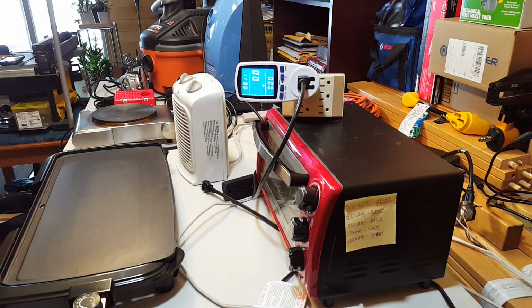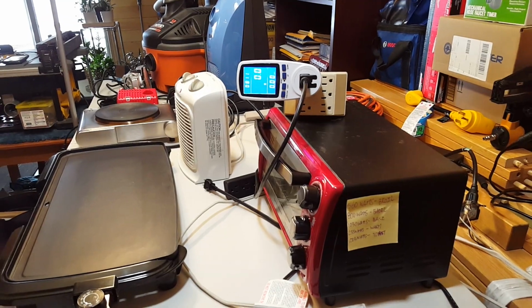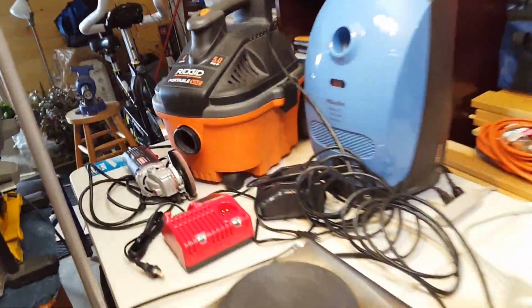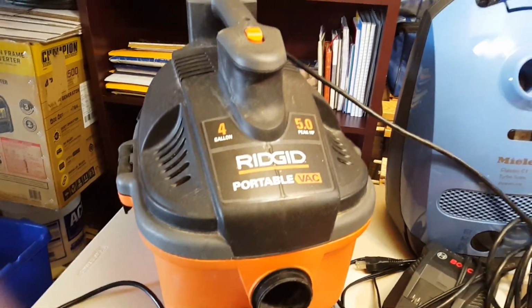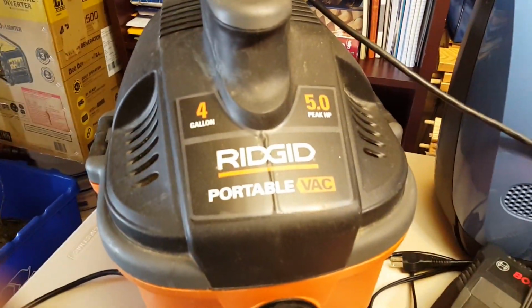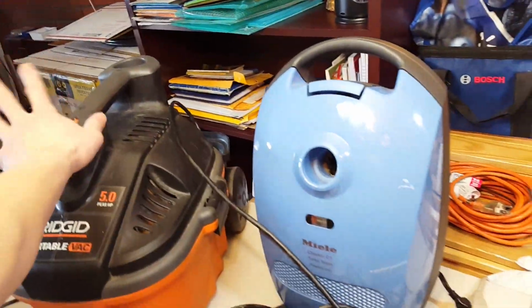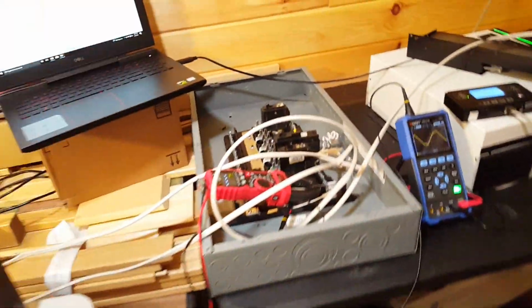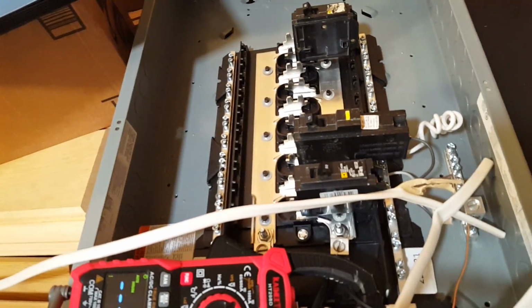We're going to look at surge, AC surge, and DC surge for the motors now. We'll start with that orange Ridgid shop vac. If you're curious which one it is, that's what it looks like. It's this one right here. It's 5 peak horsepower. It's complete BS. I'll have this switch on, and then we'll control it with the breaker over here. This is in AC inrush mode.